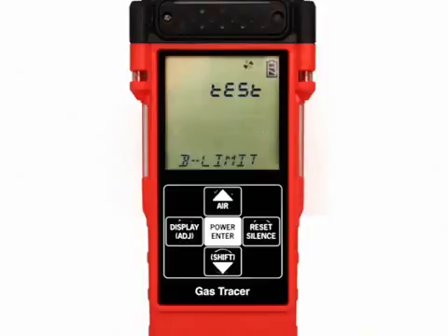If the bump reminder item in maintenance mode is turned on, the screen that appears next depends on how the bump expired item is set. If the unit is due for bump testing and the bump expired is set for confirm to use, then the test and bump limit prompt will display and the alarm LEDs and buzzer will pulse several times. When this occurs, press and release the reset silence button. You will hear a beep and the startup sequence will continue.